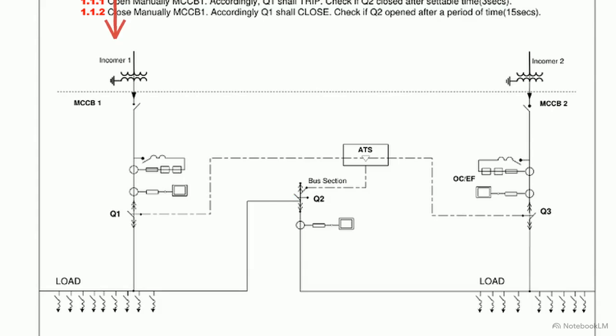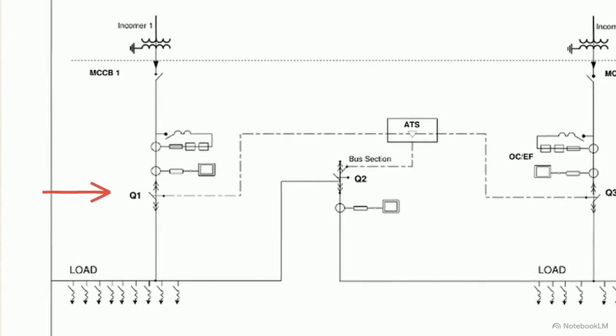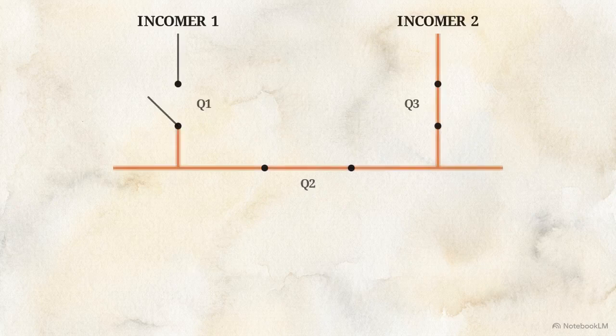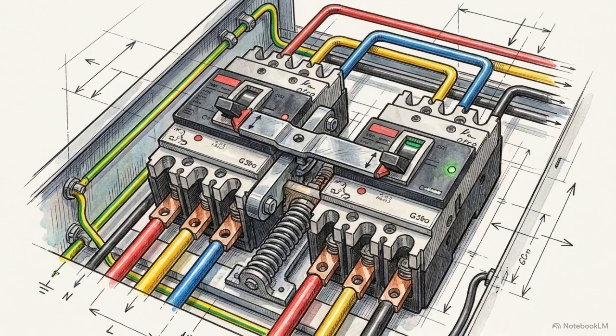The system must recognize the failure, trip breaker Q1, and close Q2 to restore power, strictly observing the approved transfer delay. When incomer 1 is restored, Q1 recloses and Q2 opens, preventing accidental parallel. Simulating a fault on Q1, the logic forces Q2 to remain open, ensuring a healthy source does not blindly feed an existing electrical fault. By exhaustively verifying the electrical and mechanical interlocks, engineers prevent catastrophic, unsynchronized parallel grid connections.